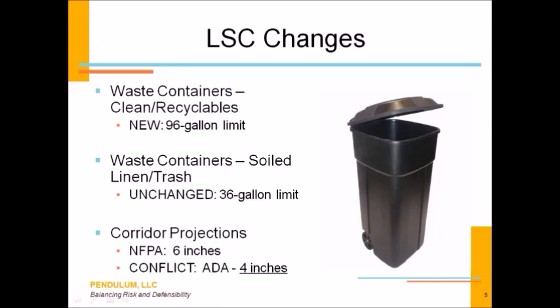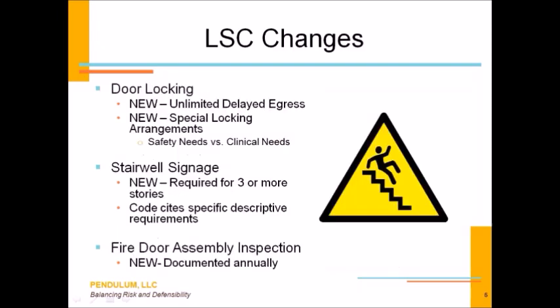But we've got a conflict, actually a couple of conflicts. One conflict is ADA. ADA says you can only project or protrude 4 inches into that minimal 8-foot wide corridor. The other conflict, if you're lucky enough to be a healthcare provider in California, that limit is even less, meaning you've got to comply with OSHPD requirements. Those of you in California know exactly what I'm talking about when I reference OSHPD. That is another regulatory agency that regulates healthcare facilities, and I believe their limit in an 8-foot-wide corridor is 1.5 inches. So you've got to know your codes, you've got to know your authorities having jurisdiction, and you've got to know what your projections can be. Now, if the corridor or hallway is wider than 8 feet, especially significantly wider, this rule is kind of null and void, because this is only applicable in 8-foot-wide corridors.